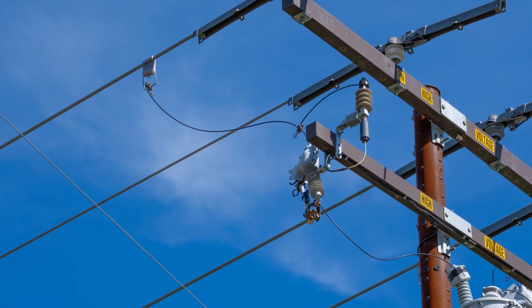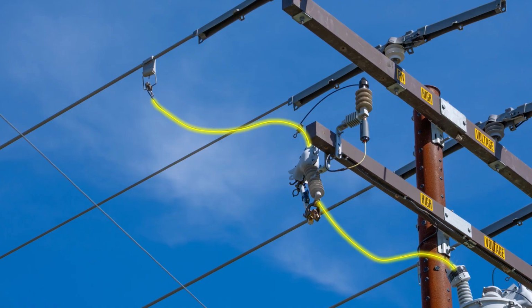Here's a newer cutout with a silicone or polymer insulator. Some utilities cover the cutout with a protective cover meant to protect birds if they should land near the energized conductors. You can see that cover right here. The crossarm mounting bracket is shown here. The upper lead is attached to the primary phase conductor with a wedge connector, a stirrup, and what's called a hotline clamp. The lower lead is shown at the bottom, connecting to the transformer bushing. Pretty cool, huh? Let's talk about this thing now.